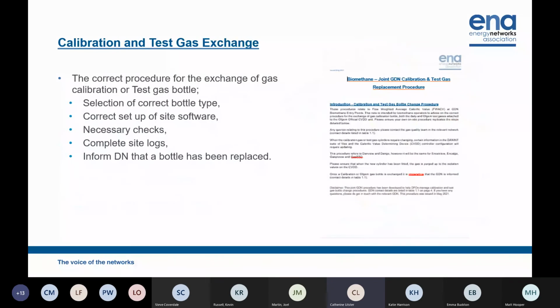So the calibration and test gas exchange. We put a procedure in place to look at the exact procedure of how we would expect the calibration bottle and test gas bottle to be replaced. I'm hoping that each site will have their own procedure on how to actually exchange the bottle itself. It's what to do with that once you've exchanged the bottle. So what the checks are that you need to carry out to ensure that the bottle has been exchanged correctly, the need to complete site logs, and that you're expected to inform your DN that the bottle has been replaced with the cylinder number, expiry date, and the composition or a copy of the certificate for that bottle. And that's for both the calibration and the test gas. It's available on the ENA website for anyone who wants to have a look at it. I'd recommend it, it's very good.